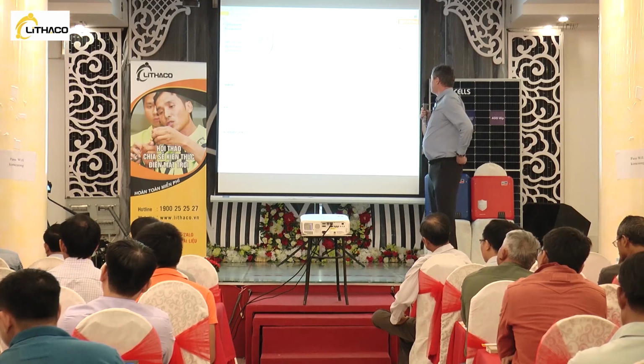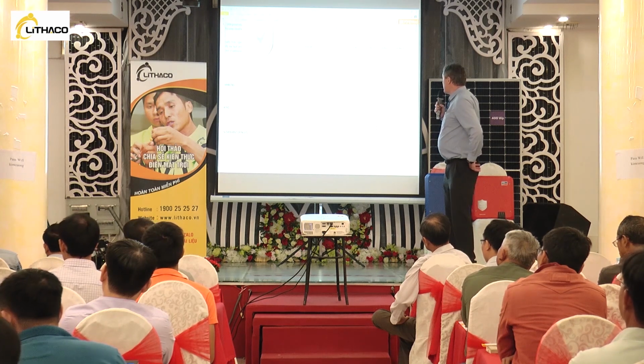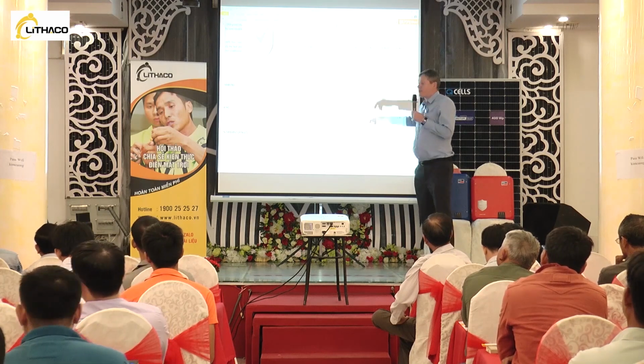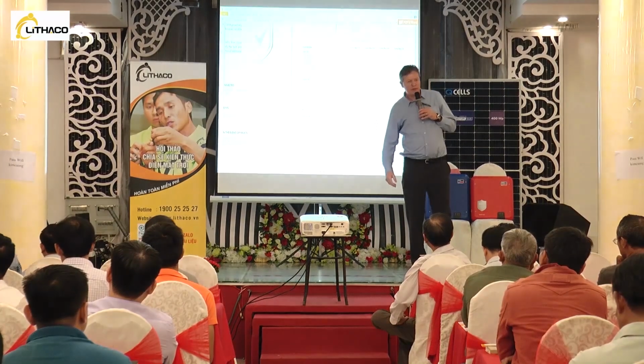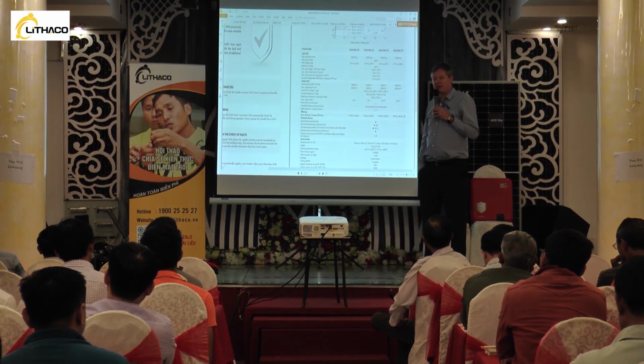So yeah, here you've got the maximum DC input voltage of 600 volts. If you put 1000 volts into it, then you'll damage it. I mean, it will switch off straight away, but it doesn't mean you didn't damage it.